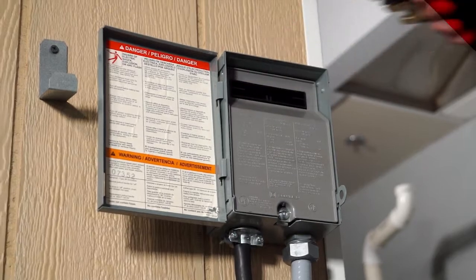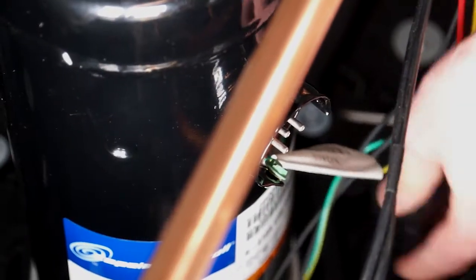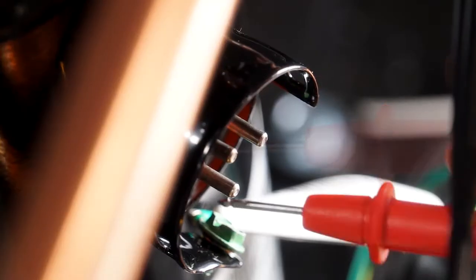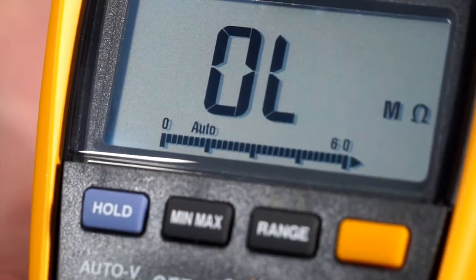To recap: kill power, remove the top, remove the compressor plug, use any copper line for ground, ohm out each terminal, and check resistance on the compressor.